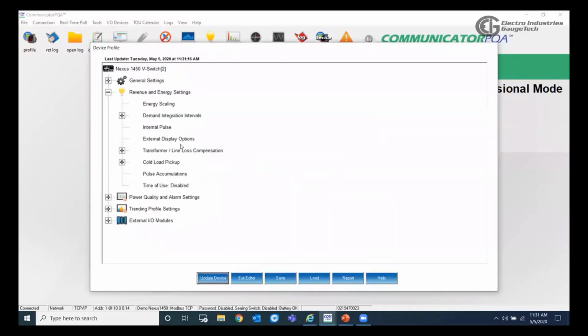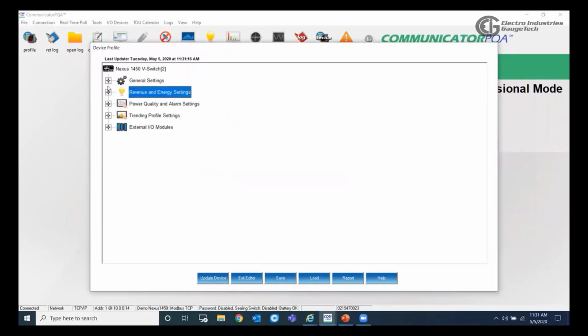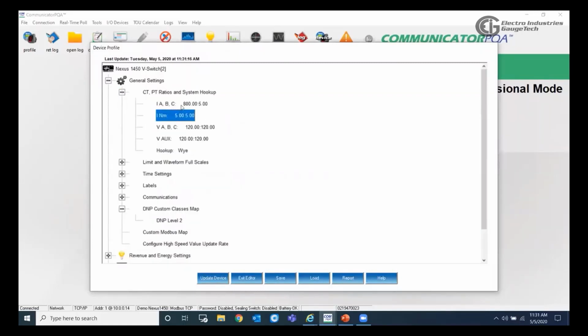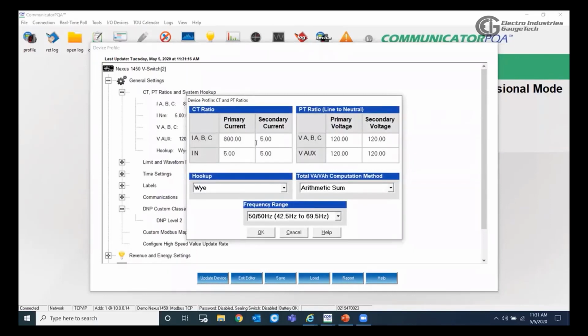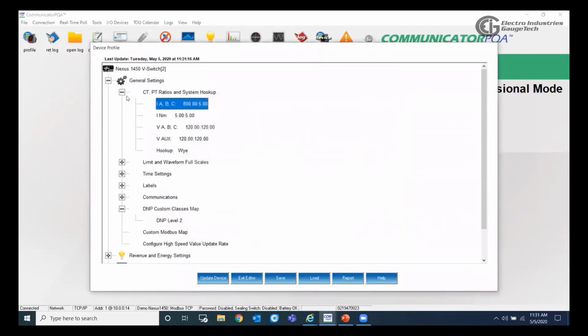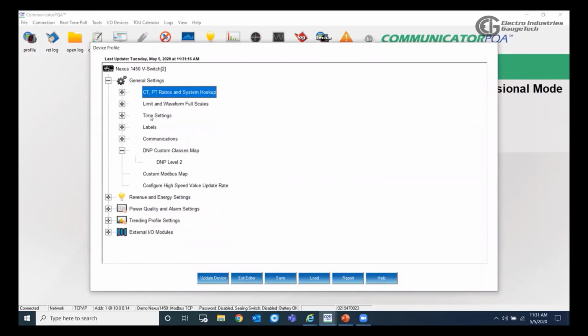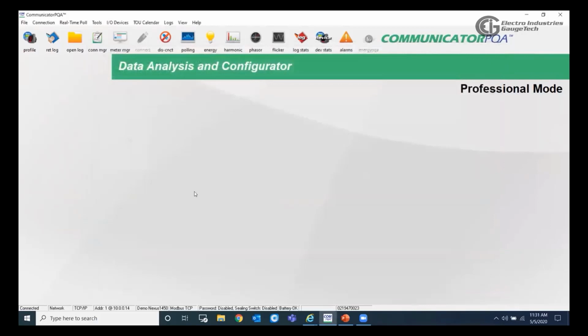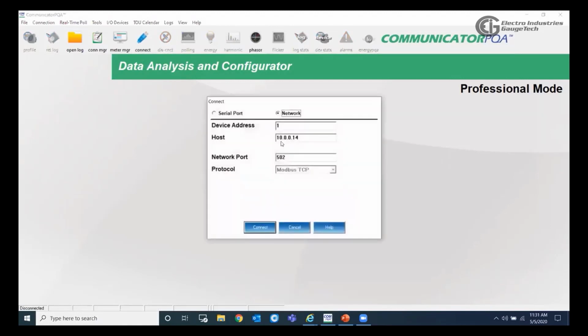Going back to the device profile after updating the new settings, you can make sure by going to the general settings and seeing that the CT ratio is 800:5 now. So that's all about the basic programming here on the profile. On the next topic, we will cover the polling screens and the reset of the meter. To do that, I will be connecting to another meter to have real-time data, so I will use one of our demo meters in the office.